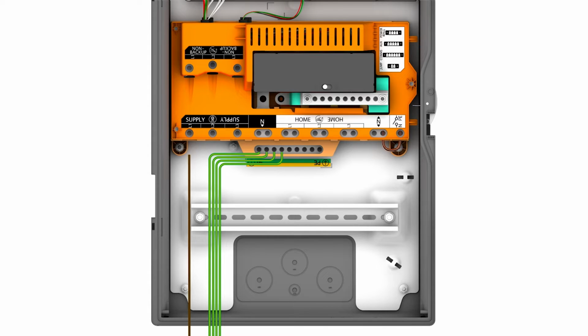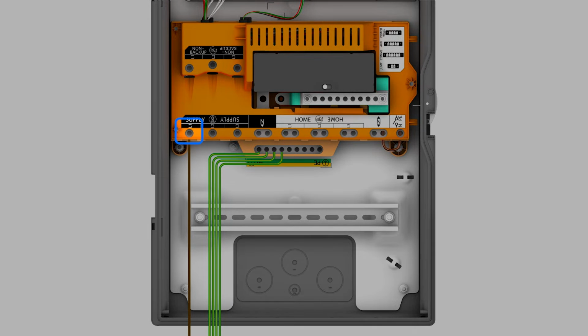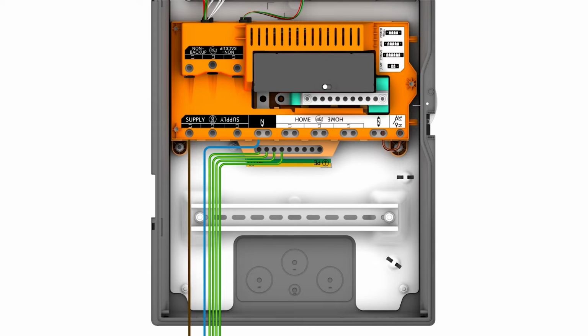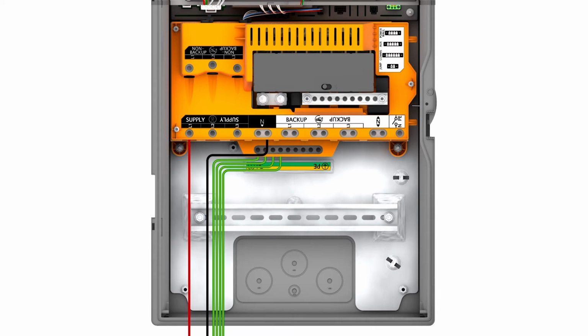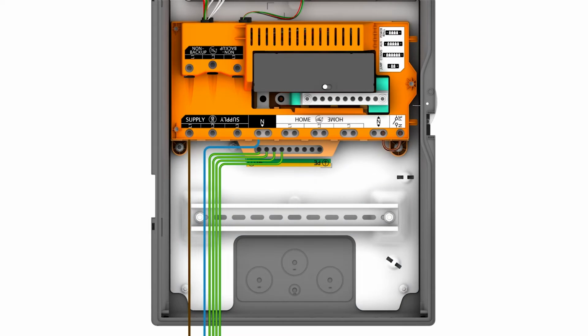Begin with the incoming supply wiring. For single-phase systems, land the incoming Line 1 conductor on the terminal labeled Supply Line 1 on the black label. Land the incoming neutral conductor to the Supply Neutral terminal. Please note that wiring color conventions vary by region, and the following examples may not match a specific installation. Follow the installation manual and local standard practices throughout the process.